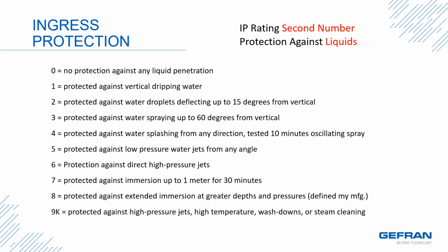6 is protection against direct high-pressure jets. 7 is protected against immersion up to 1 meter for 30 minutes. 8 is protected against extended immersion at greater depths and pressures. 9K is protected against high-pressure jets, high temperature, washdowns, or steam cleaning.